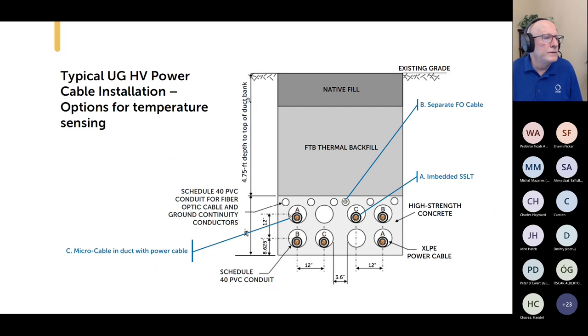To illustrate what I'm talking about here, here's just a typical duct bank installation. Here's your ground level. You've got dirt. You've probably put thermal backfill below the dirt. And then here's your concrete with your ducts in it. With the embedded stainless steel loose tube concept, you would put the tube just underneath the outer jacket, typically, or mixed with what comprises the sheath. For those of you who may be looking on mobile phones, you may not be able to see this well. Just get the concept that you've got a very small tube with fibers underneath the jacket. The separate fiber optic cable would be installed in a separate duct. Now, it could be any one of these, as you see in this picture. I just plopped it here.